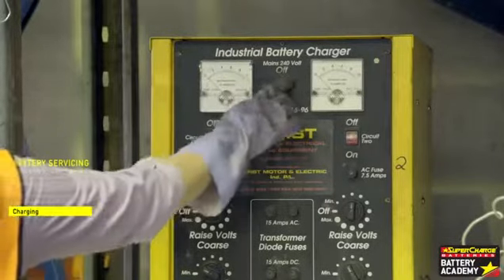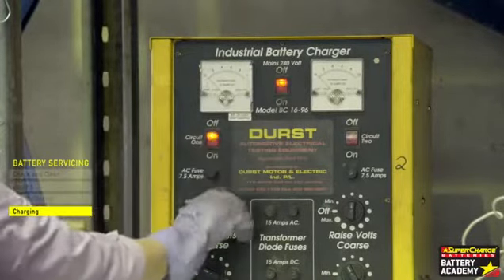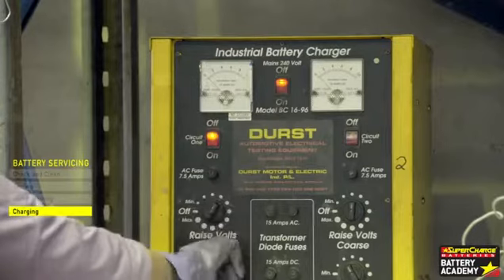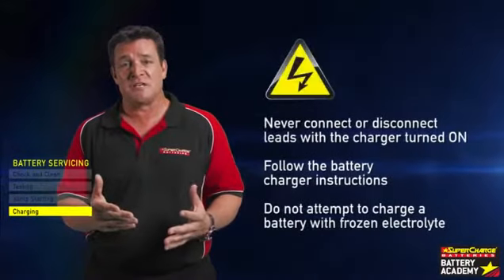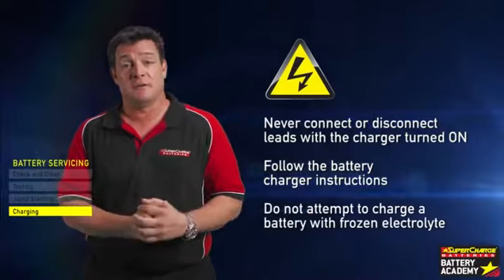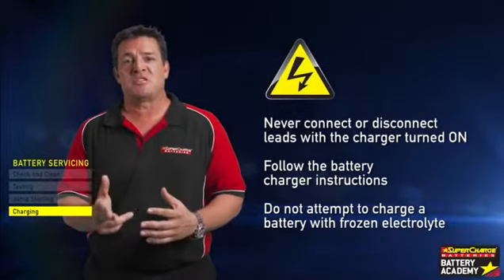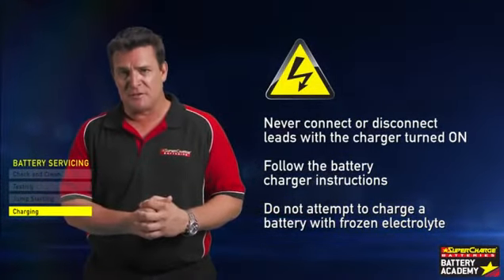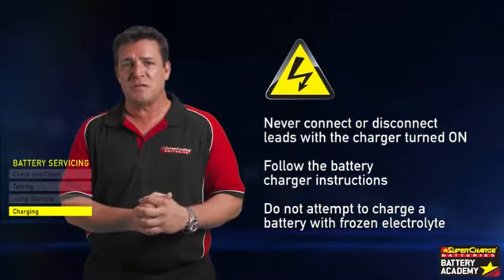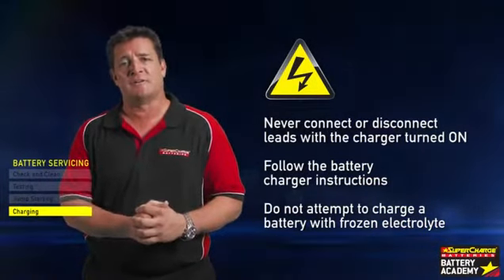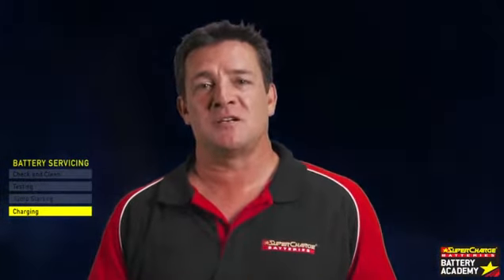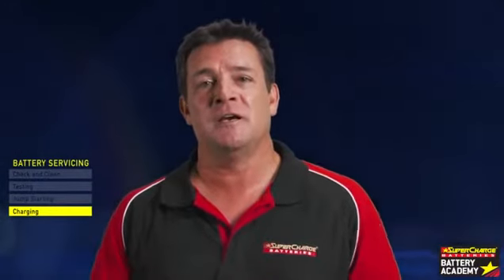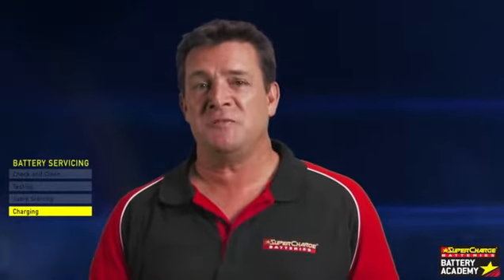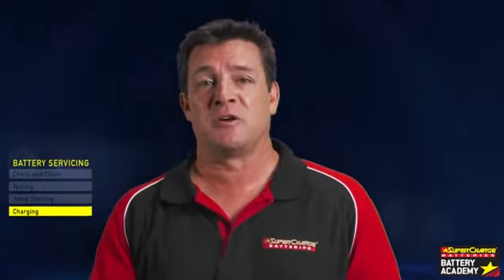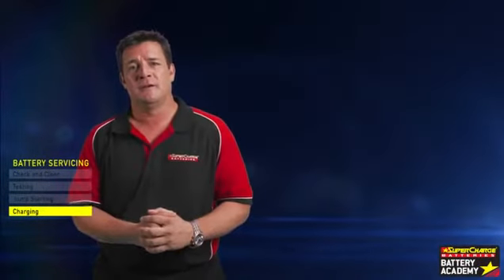An electric current is applied to the battery to reverse the chemical action in the cells. Never connect or disconnect leads with the charger turned on. Follow the battery charger manufacturer's instructions and do not attempt to charge a battery with frozen electrolyte. The battery can be considered fully charged when all cells are gassing freely and when there is no change in specific gravity or on-charge voltage readings for more than 1 hour.